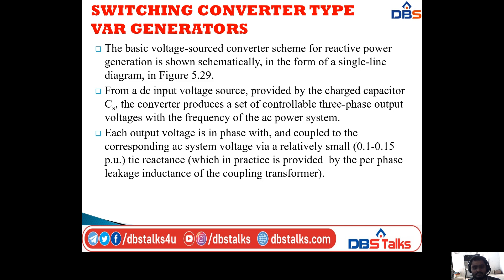By varying the amplitude of the output voltages produced, the reactive power exchange between the converter and the AC system can be controlled, similar to a rotating synchronous machine. If the output voltage amplitude is increased above that of the AC system, current flows through the tie reactance from the converter to the AC system, and the converter generates reactive power for the AC system.